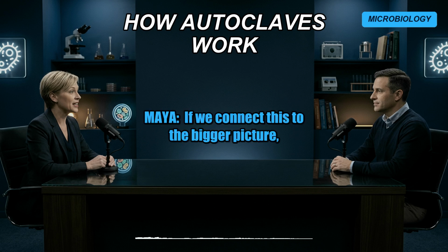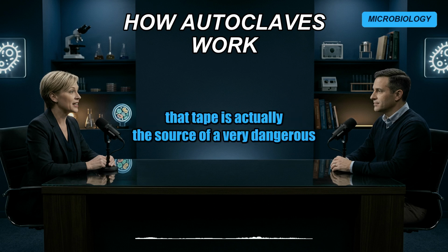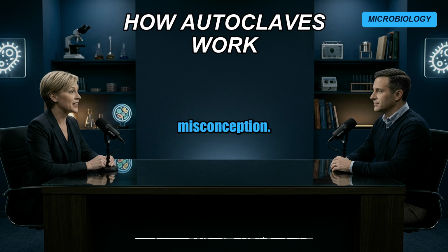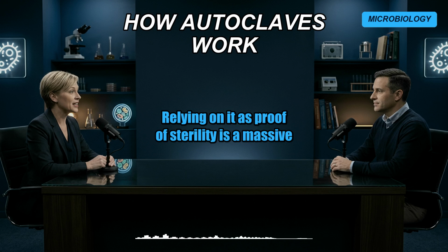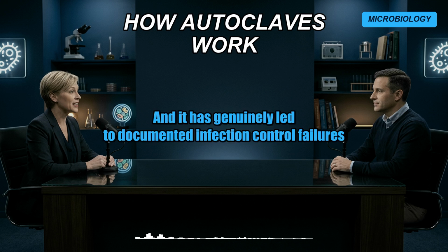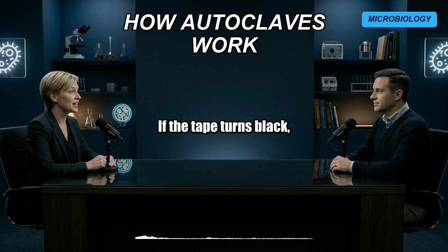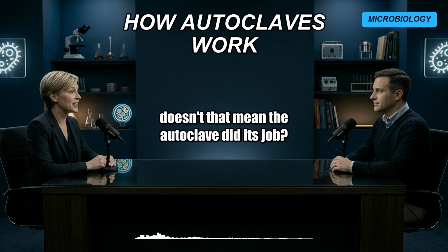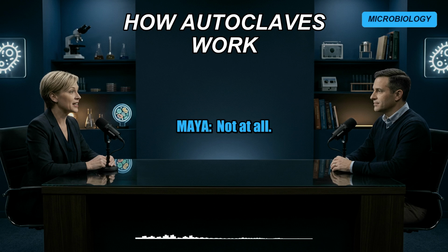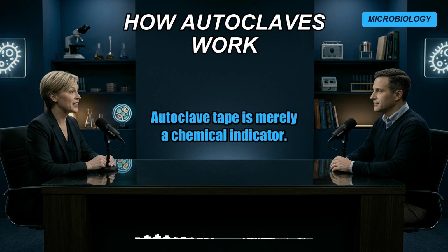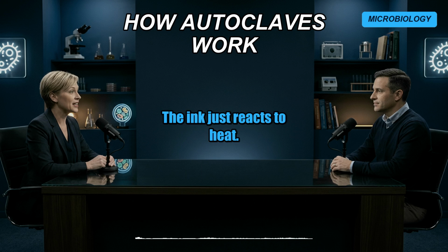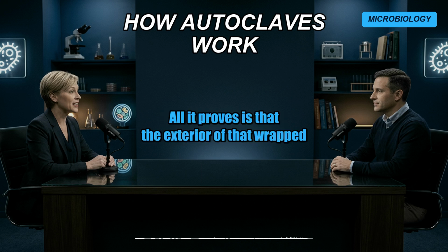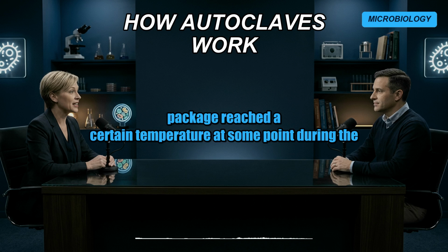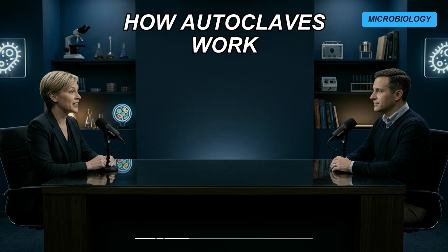If we connect this to the bigger picture, that tape is actually the source of a very dangerous misconception. Relying on it as proof of sterility is a massive trap, and it has genuinely led to documented infection control failures in clinical settings. Wait, really? If the tape turns black, doesn't that mean the autoclave did its job? Not at all. Autoclave tape is merely a chemical indicator. The ink just reacts to heat. All it proves is that the exterior of that wrapped package reached a certain temperature at some point during the cycle. Oh, wow.